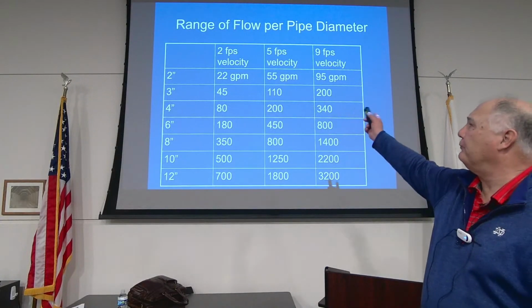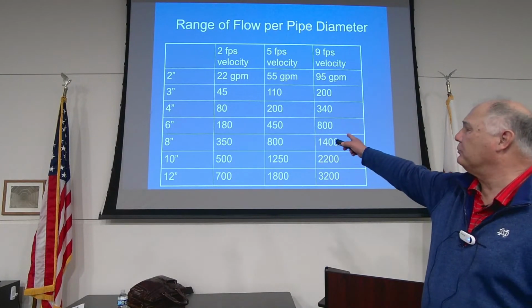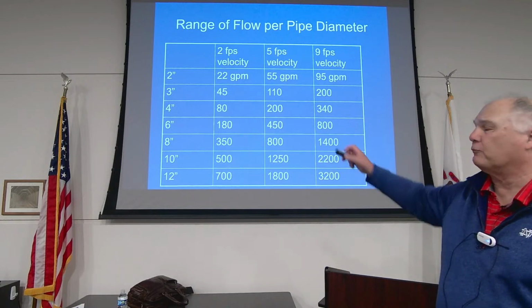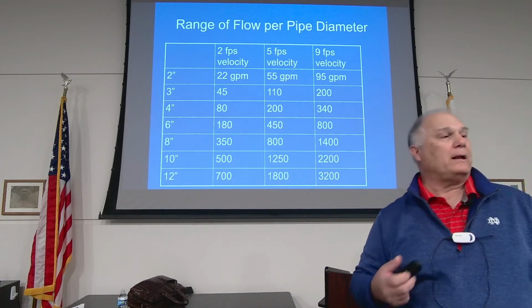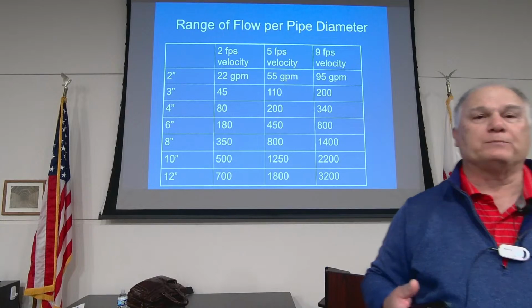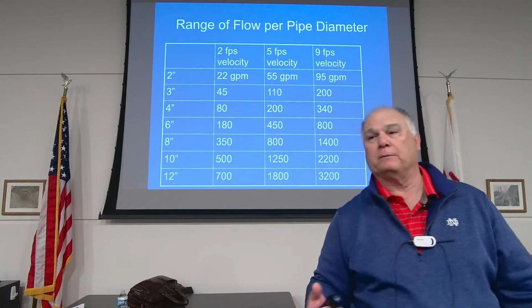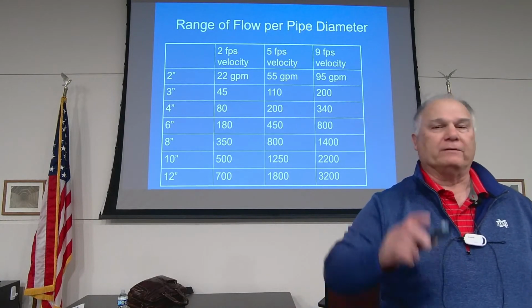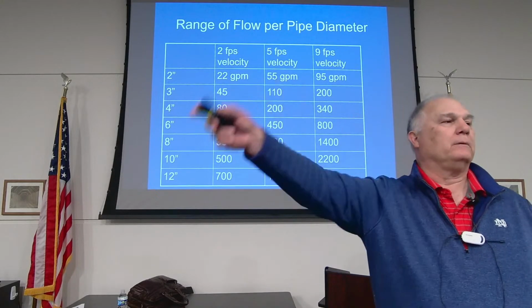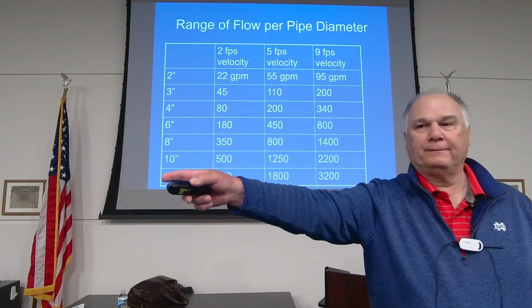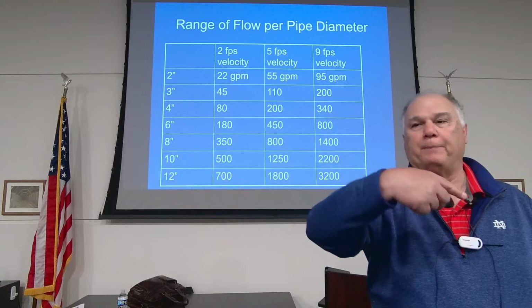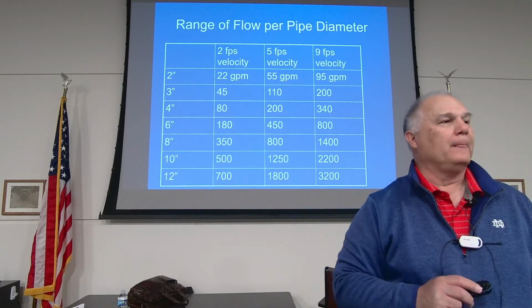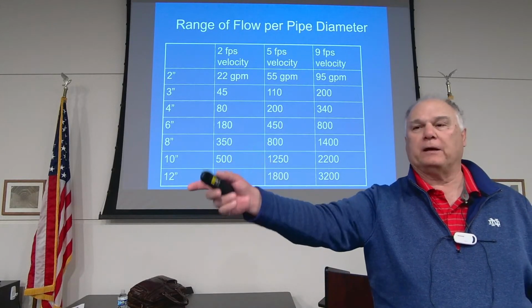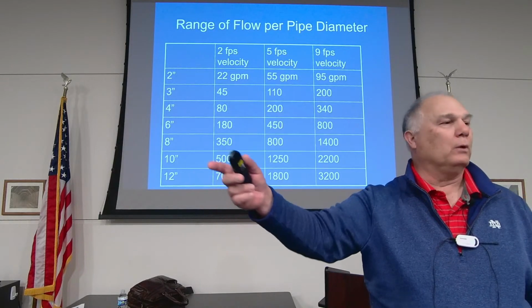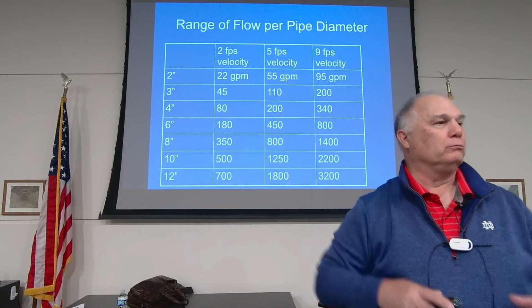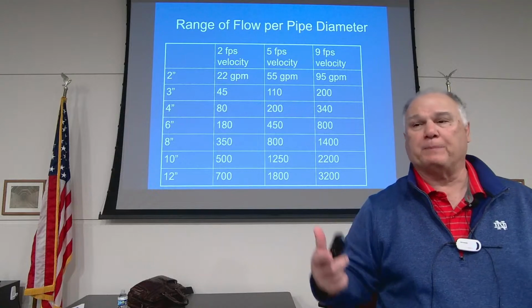If we look at 2 feet, 9 feet, so at 6-inch pipe, we'll do 450. A 10-inch pipe, we'll do up to 1,200 gallons a minute. A lot of times we get in situations where we have, especially for developments that are expanding, communities that are expanding, we have a guy that wants to build a subdivision half a mile out of town. Put a pump station out there and bring it back. Okay. So, but he only wants to put in a pump station that's going to do whatever pipe he wants to do. Because he's going to probably be responsible for that pipe.